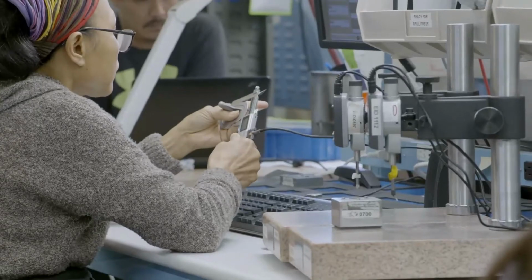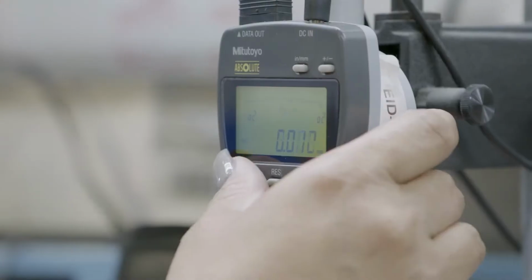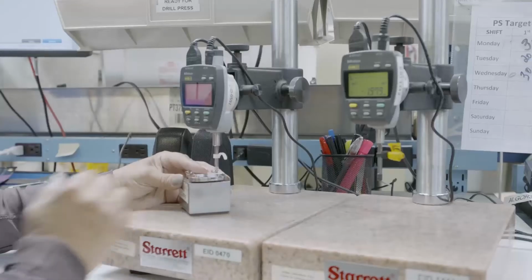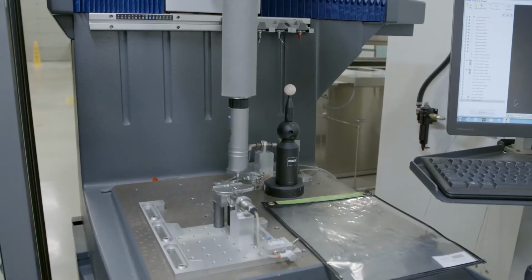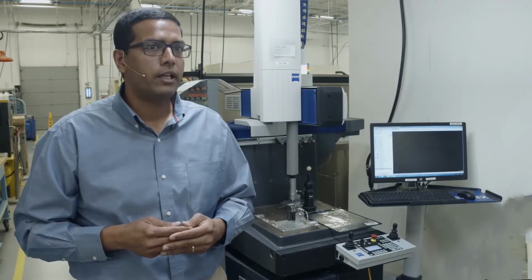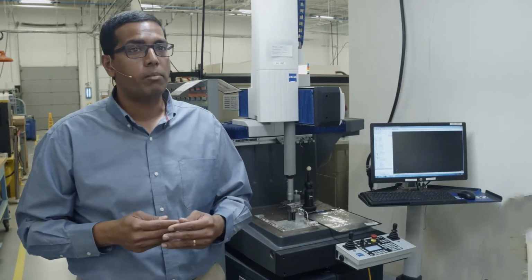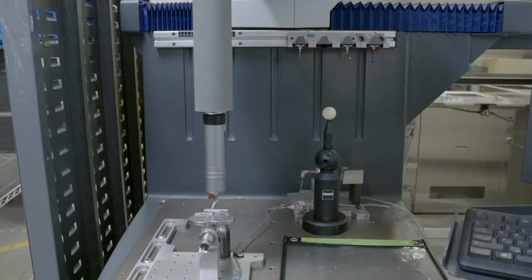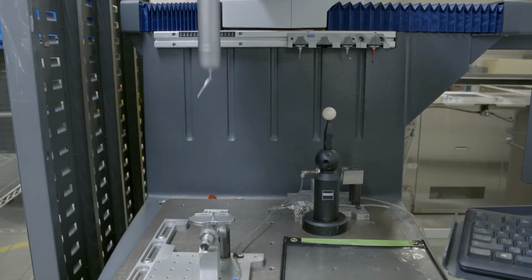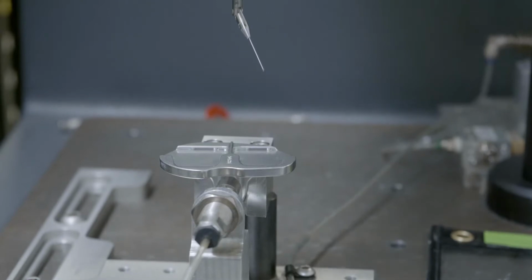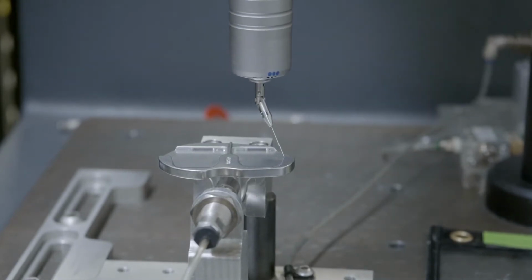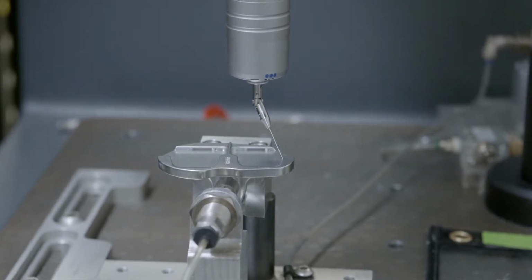This is one of the many inspection steps that are performed during the manufacturing process where we ensure quality in every part that we make. All of the patient-specific features are confirmed and inspected against the original CAD design. This is another inspection step within our manufacturing process using an automated CMM machine, which is using highly precise ruby tip probes to confirm accuracy to the patient-specific design, measuring accuracies up to 3 to 5 microns, ensuring patient-specific performance.